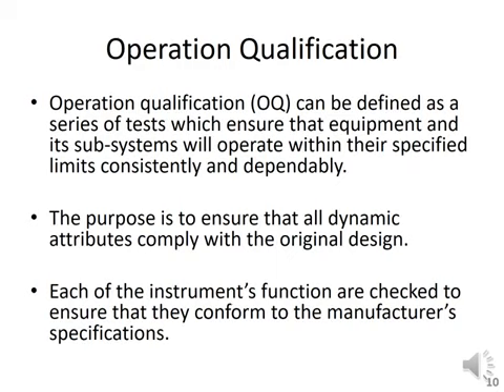This is very important. This is usually performed before the system is released for use by the customers, by the consumers. Okay, or in other words, if you are talking about an instrument, we would say that operational qualification is usually performed before the instrument is handed over for use, right? So the purpose is to ensure that all the dynamic attributes comply with the original design of the machine, or original design of the work. Okay, so each of the instrument's functions are checked to ensure that they conform to the manufacturer's specification. This is important. If you confirm proper functioning of the machine beforehand, in the long run you are not going to face any difficulty, and it will be working smoothly and nicely.